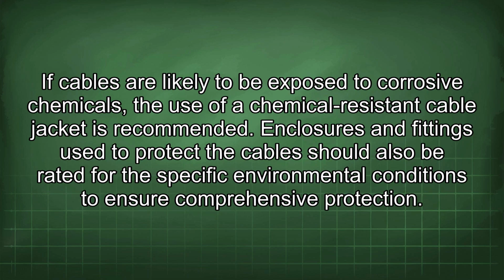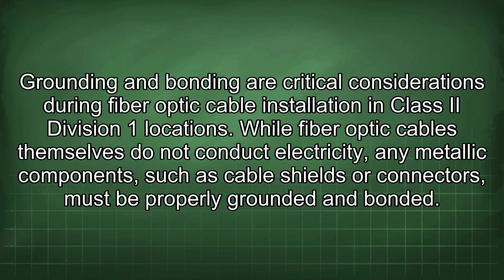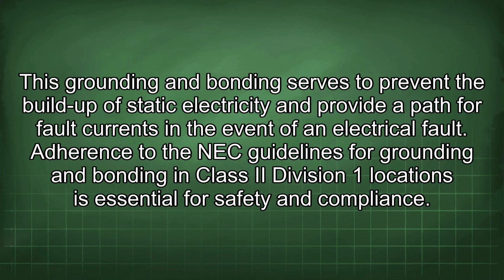If cables are likely to be exposed to corrosive chemicals, the use of a chemical-resistant cable jacket is recommended. Enclosures and fittings used to protect the cables should also be rated for the specific environmental conditions to ensure comprehensive protection. Grounding and bonding are critical considerations during fiber optic cable installation in Class II Division 1 locations. While fiber optic cables themselves do not conduct electricity, any metallic components, such as cable shields or connectors, must be properly grounded and bonded. This grounding and bonding serves to prevent the build-up of static electricity and provide a path for fault currents in the event of an electrical fault.